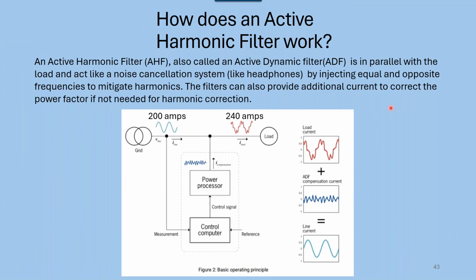The second is an active harmonic filter. And that's very easy to understand because it works just like noise canceling headphones. Whatever harmonics I've got being generated, the filter cancels them and you end up with a beautiful line current. What's interesting about an active harmonic filter is that it's in parallel with the load. So if something happened to my filter, I could disconnect it and I'm still running, with no effect on the system. So they're really nice from this standpoint, okay? It's a great solution, but it's more expensive than passive filters. But it works, it's going to truly cancel out all the harmonics.